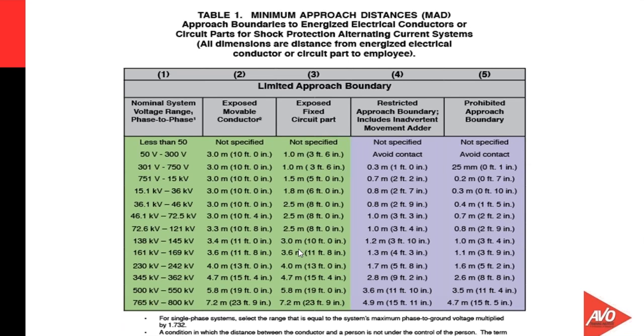So this is voltage rated, so you go by the test voltage that you're actually using, and that gives you the approach dimension. This test area dimension has a couple of boundaries to consider. One of them is the limited approach boundary by unqualified persons to the actual voltage of the parts that we're testing or that we have live. The other issue would be a potential arc flash boundary. If there are other systems or other components in the system that we're testing that are adjacent to us and energized, then obviously we would have approach distances to live parts there to deal with, but you may well have to deal with the arc flash zone as well. One of the things that takes precedence over all of this is making sure we have enough room.